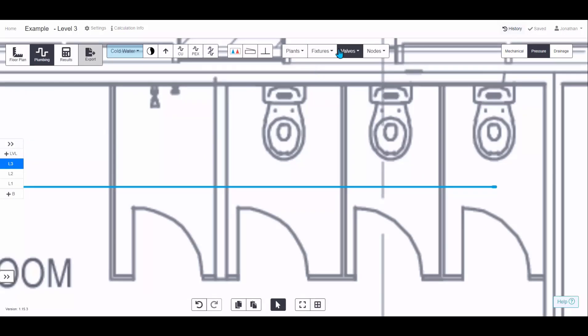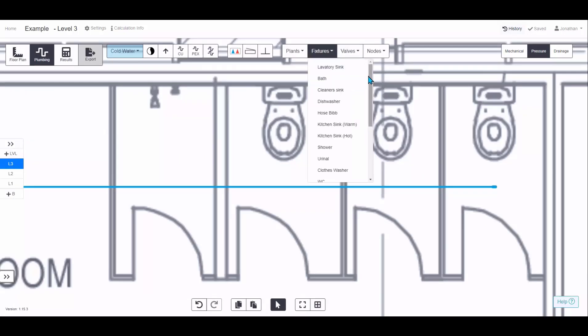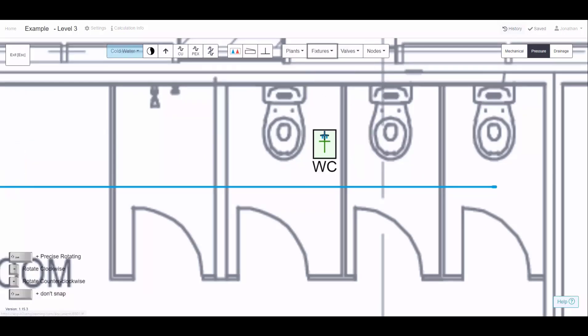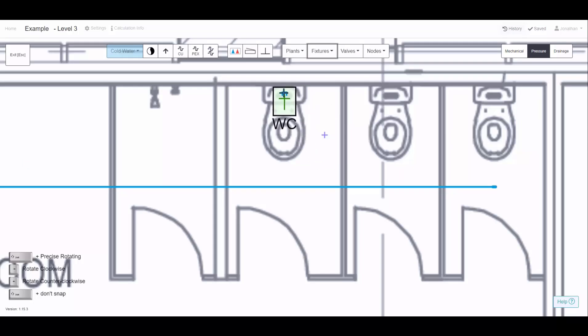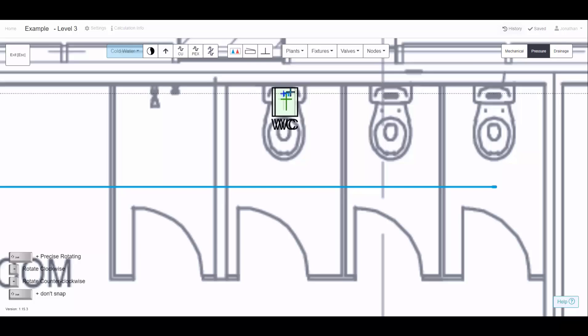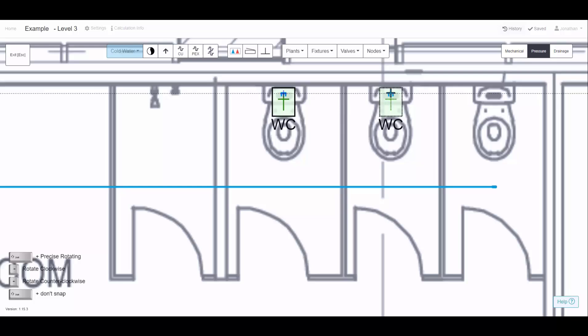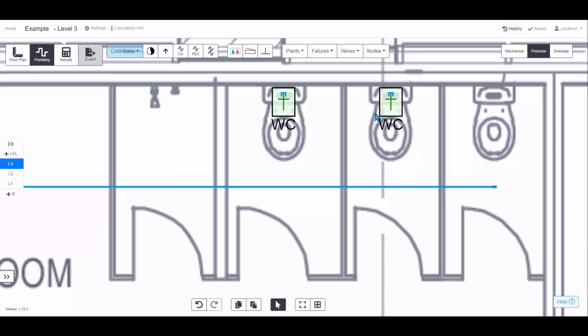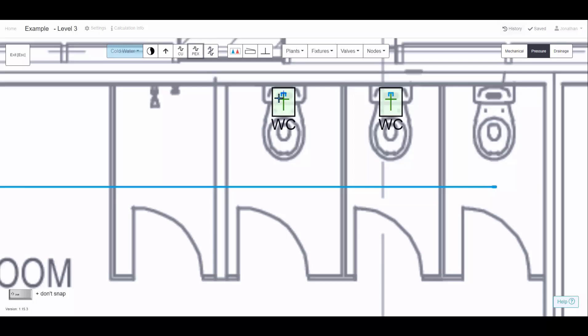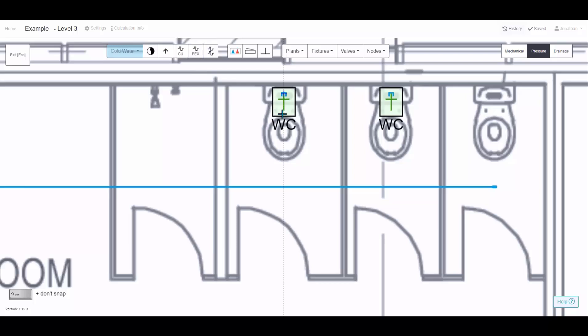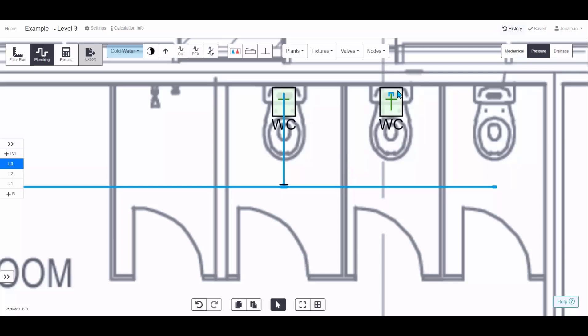But for fixtures that we do have, choose it from the drop down menu, you can rotate that with the arrows on your keyboard, and then stamp it on top of where the architect has shown it. If you hover over a fixture, it will bring up this black line. So to get them all neatly aligned, you can do that. I'll just do two because there's two ways to connect them up. One way is to manually draw the pipe, so you can hover over it, click and connect to the nearest pipe. As that cap disappears, you know you've connected to it.